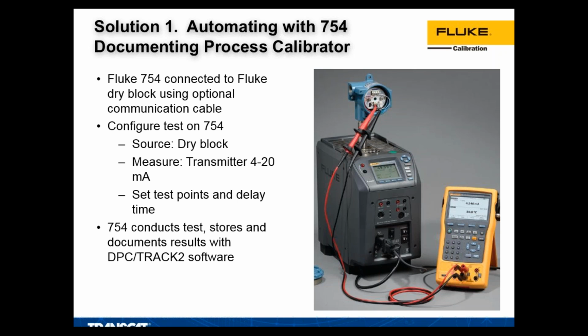And then you can measure whether it's a thermocouple output or a 4 to 20 milliamp transmitter. We're going to go through an example of doing it with a transmitter. You can set up a simple routine that'll go through various temperature points, and we'll discuss how that works.